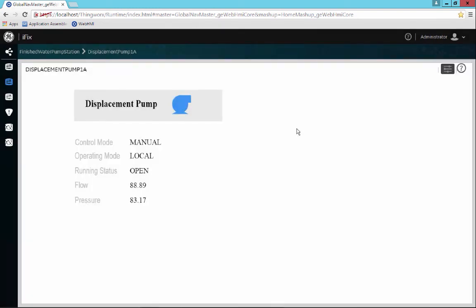We also provide data validation. If they type something in out of range, they would get a warning message saying the value you are typing in is not within the operating limits. Also, if a user doesn't have credentials, they would also see messages saying they don't have credentials to interact with this style of information. All of this gets pushed into our audit trail, which is on the SCADA server as opposed to the client, and it's there for a full audit trail for after-the-fact analysis of your process.